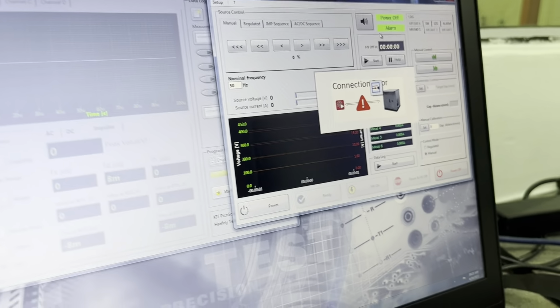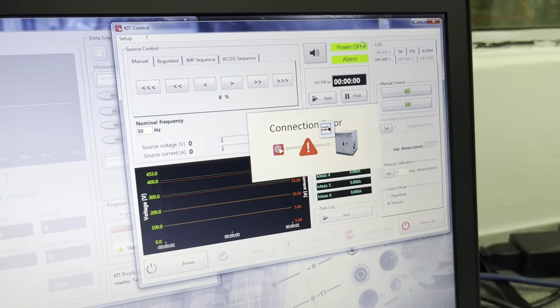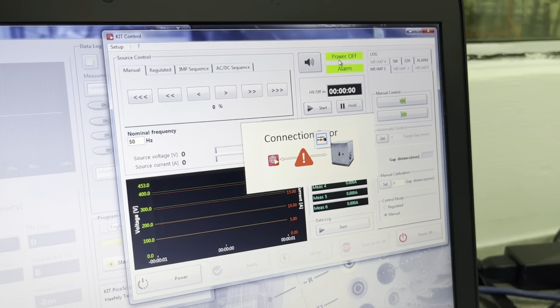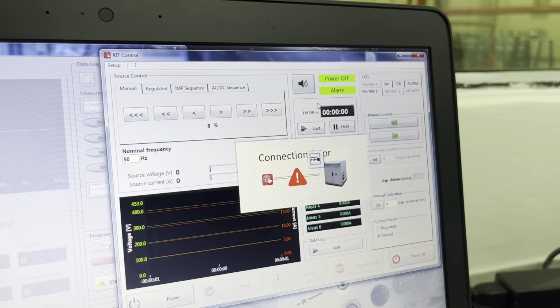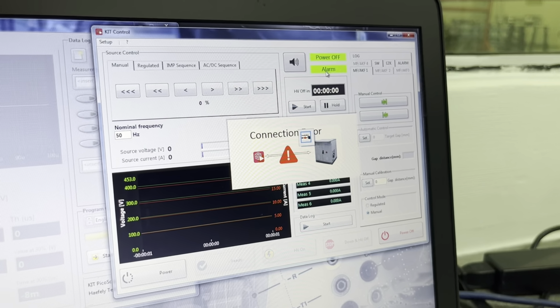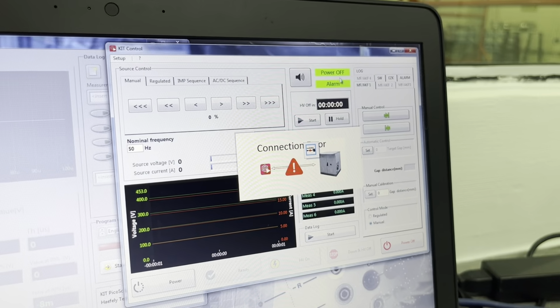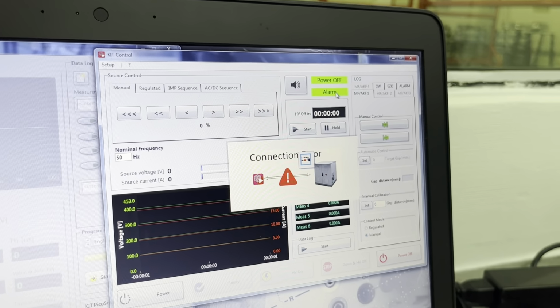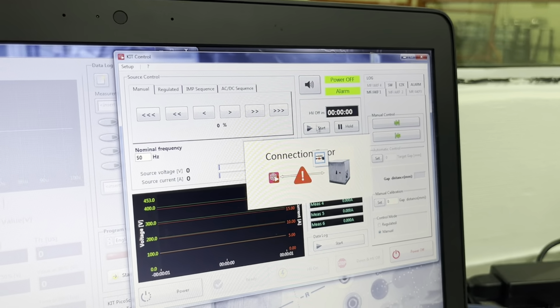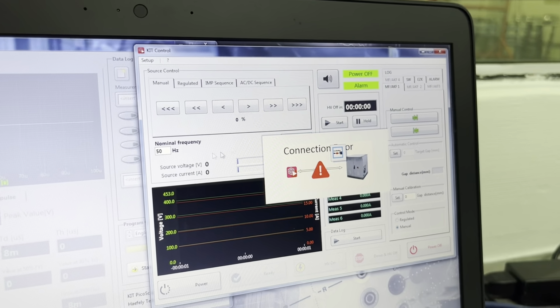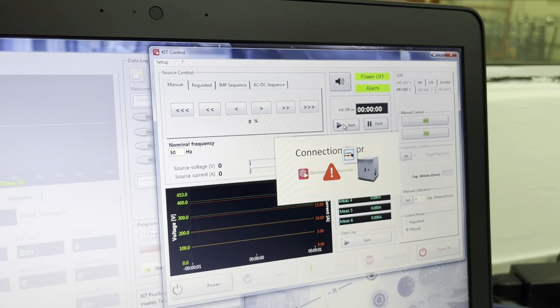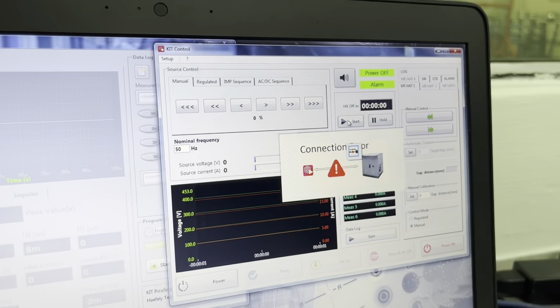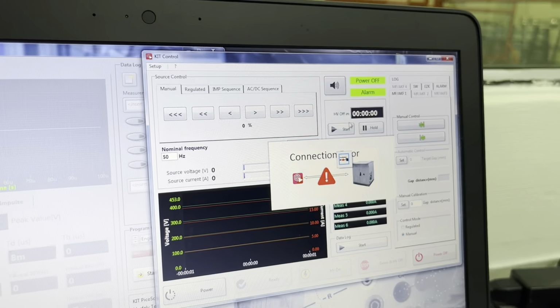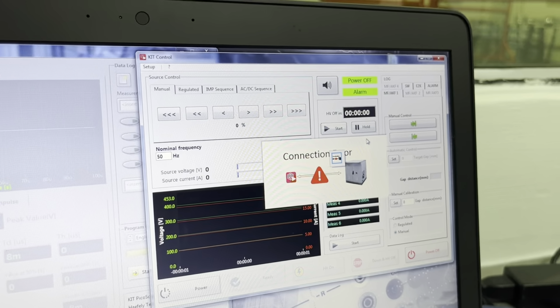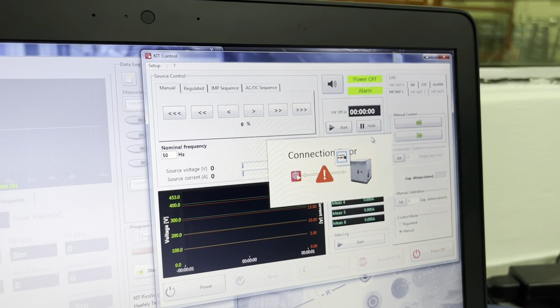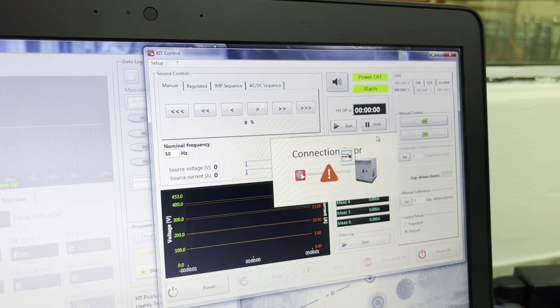Okay. So this is the indicator alarm. Whenever any interlock is breached, the alarm will turn red, so we cannot operate our HV. Once we set our primary, we can just press start, and in 7 seconds we have to press start again. This is a safety, double safety for our operation.